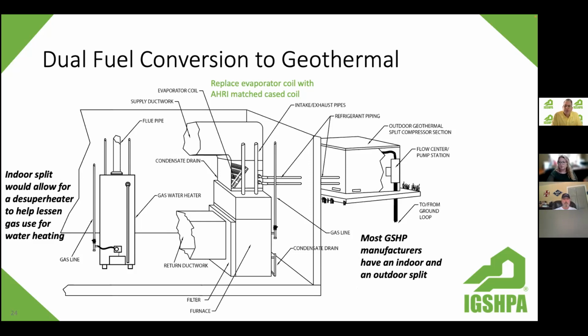It's a much better approach than an air source dual fuel because of that balance point. If you remember, the air source system had a 31-degree balance point. Well, at that point, we're going to be doing a majority of our heating, depending upon the climate, with the furnace. We can't run the heat pump and the furnace at the same time. It's an either or situation. With Geo and our lower balance point, this furnace stays off in the example we had until 16 degrees outside. So the vast majority of it's done with geothermal. Just something to consider.